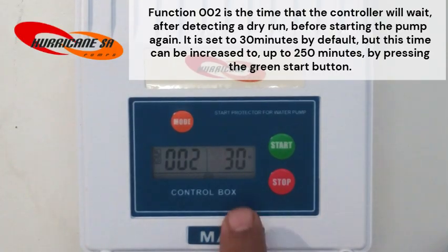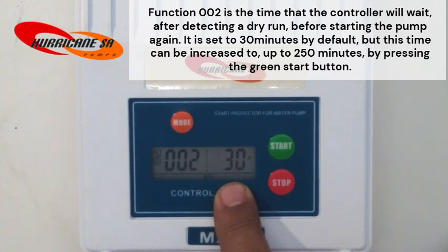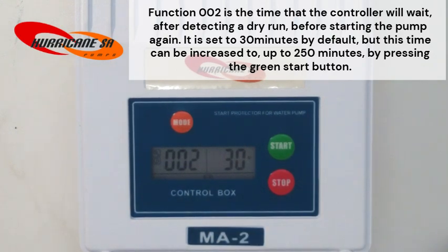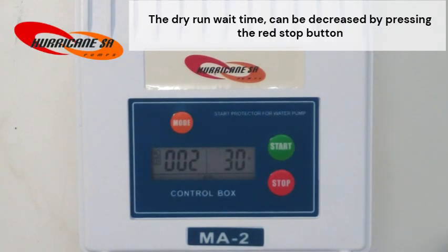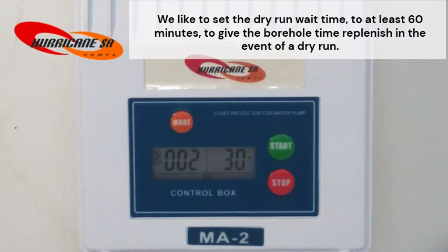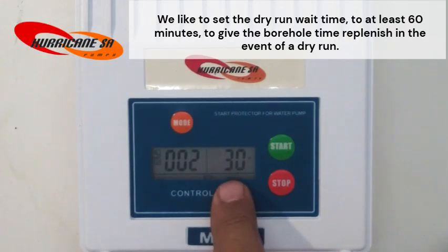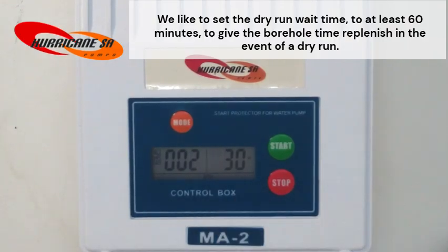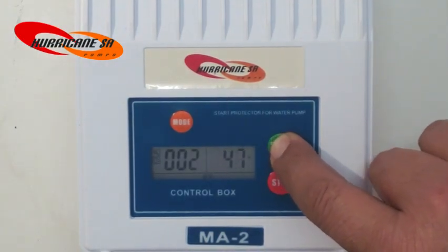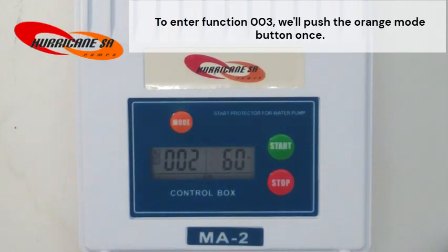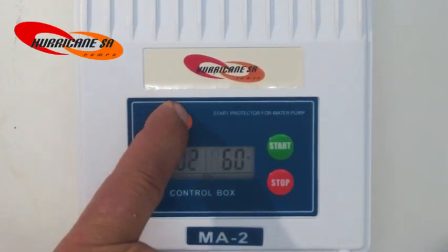It is set to 30 minutes by default, but this time can be increased to up to 250 minutes by pressing the green start button. The dry run wait time can be decreased by pressing the red stop button. We like to set the dry run wait time to at least 60 minutes to give the borehole time to replenish in the event of a dry run. To enter function 003, we'll push the orange mode button once.